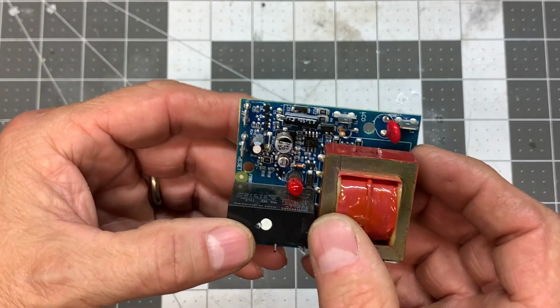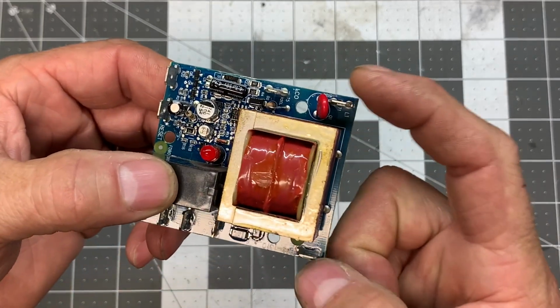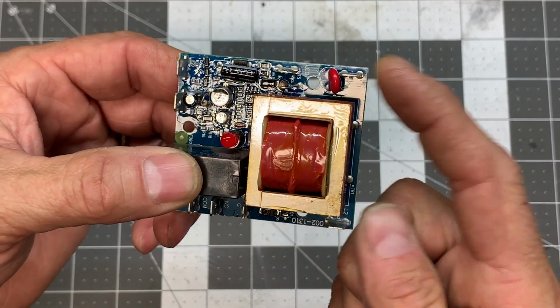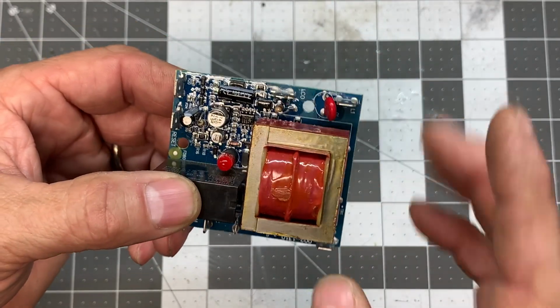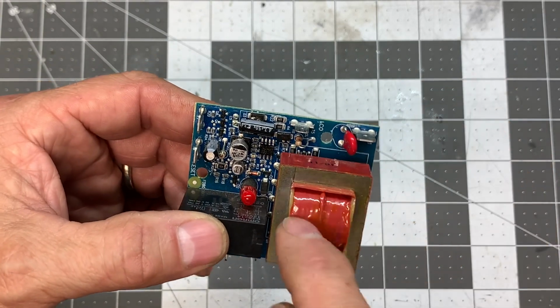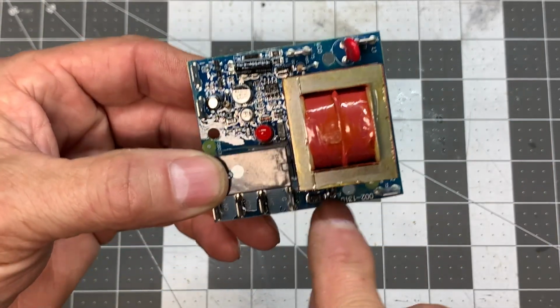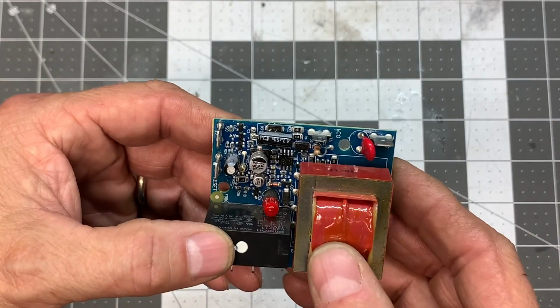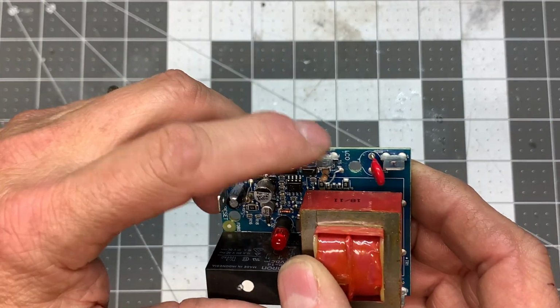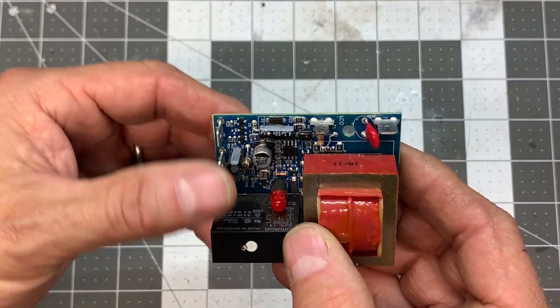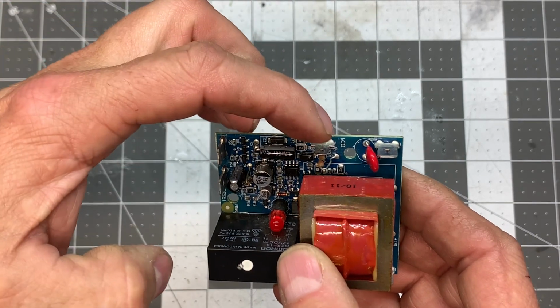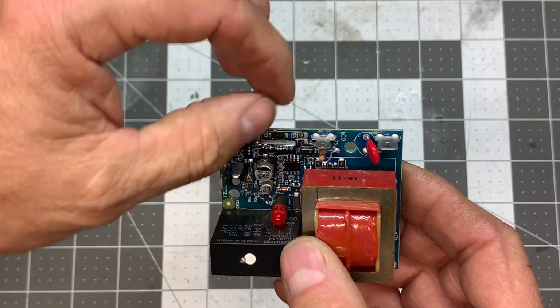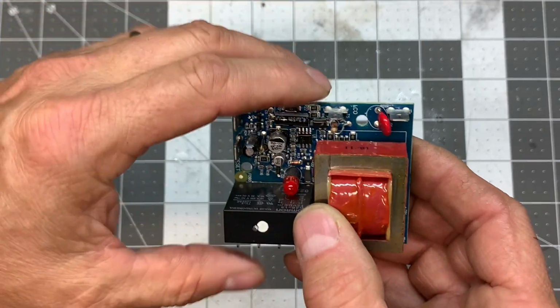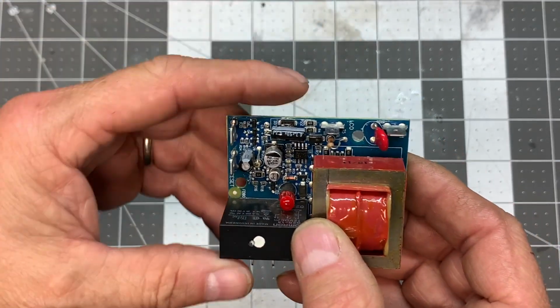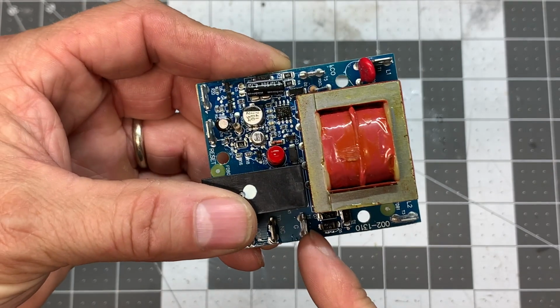But basically, the way this works is that there's 120 volts here on these two terminals, line 1 and line 2, and that drives this transformer. And then the transformer secondaries are rectified here with the diodes and filtered and so on and so forth. Then there's a low water cutoff sensor that's just a probe that sticks into the boiler vessel and measures resistance based on between the low water cutoff probe that is into the boiler vessel and the ground lead of the vessel.